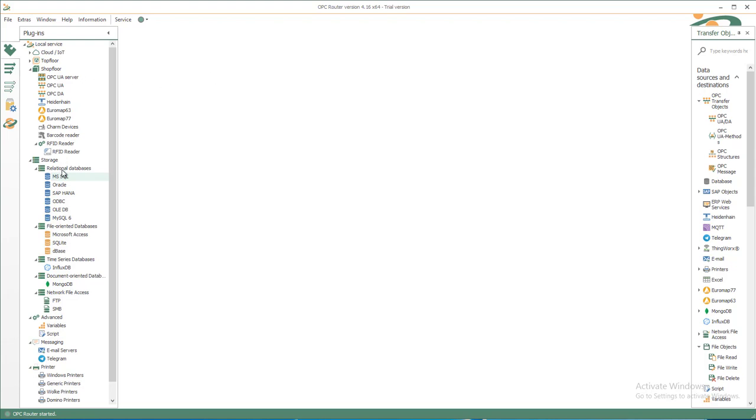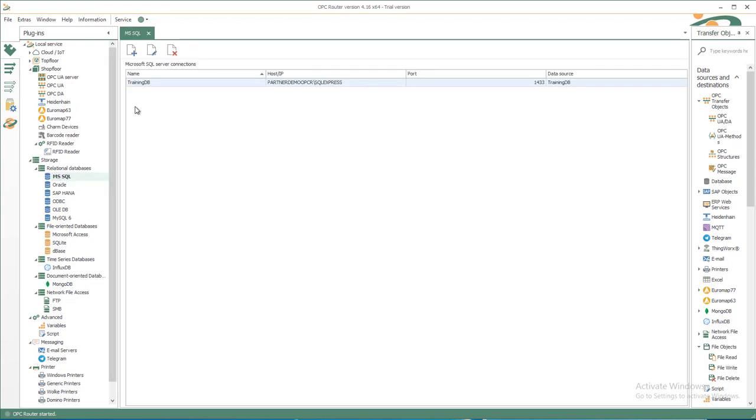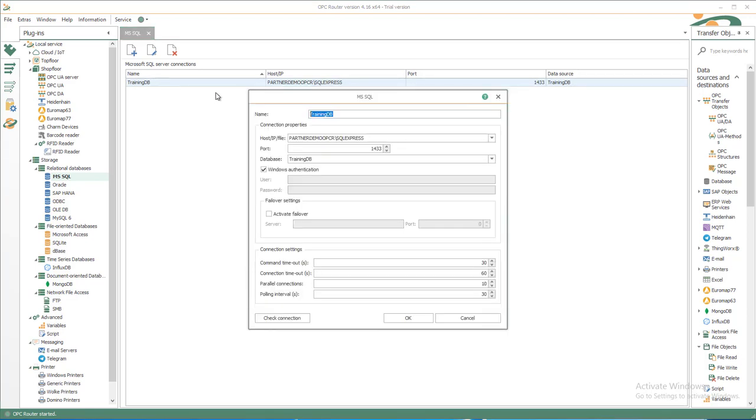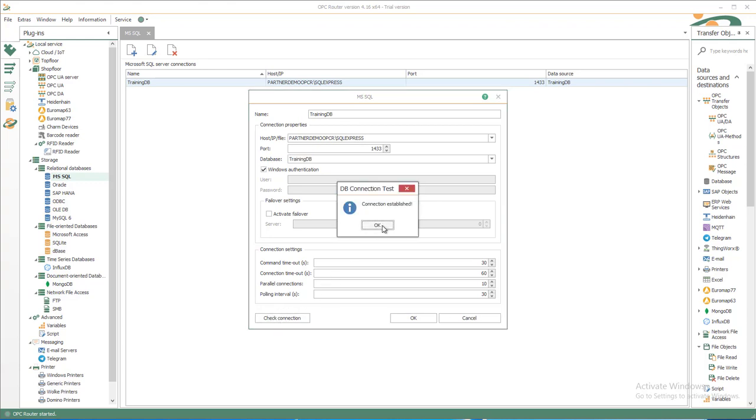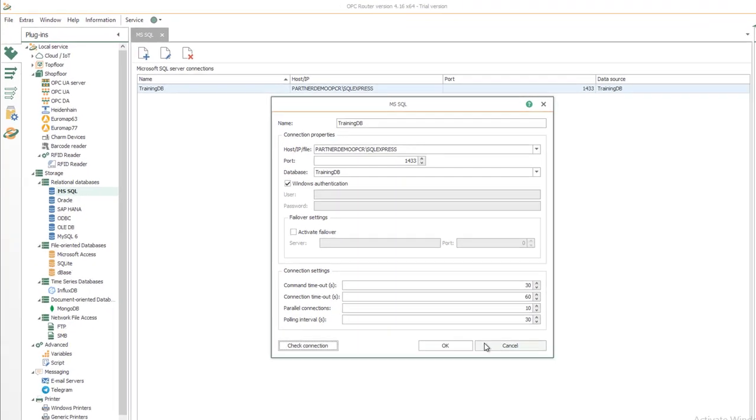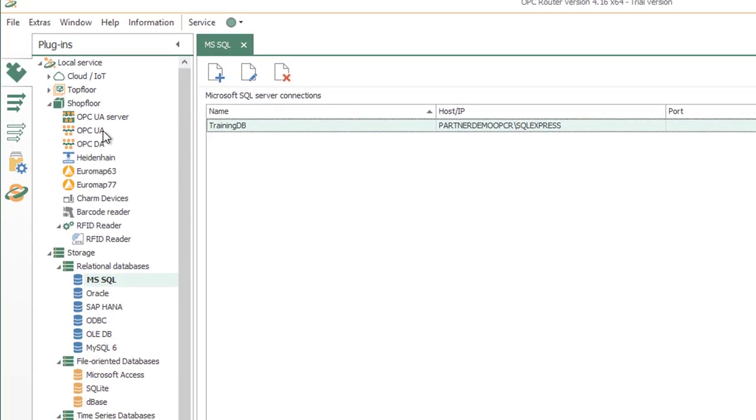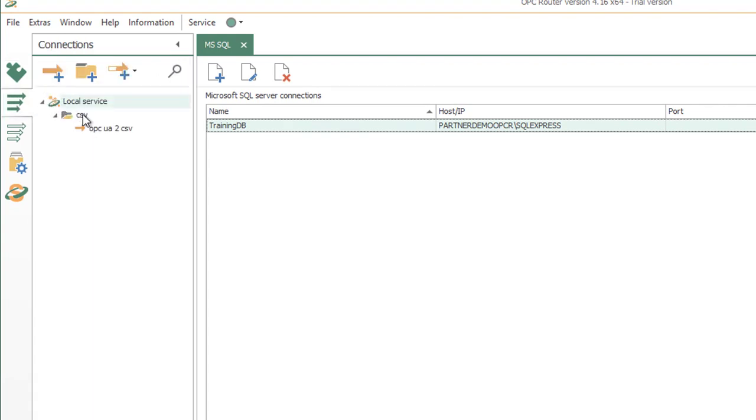First we connect to the database systems under Storage, Relational Databases, MS SQL. I have prepared a training database target called TrainingDB via SQL Express instance with Windows authentication. I used the Windows user also with my runtime service and background. If you want, you could also use username and password instead for a SQL user, and then you can drop down the databases available and select TrainingDB in my example. You don't need to check connection in addition because if you can drop down the databases, then you have connection to your database system.